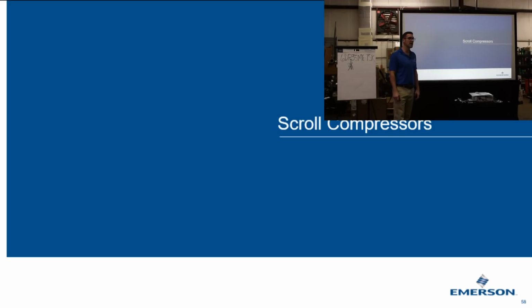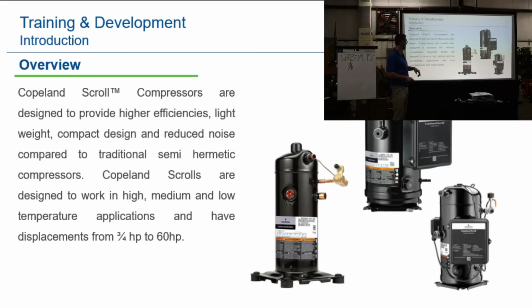Okay, scroll compressors. How many people work on scroll compressors today? Every hand goes up. Because this is most of my classes that I do, everybody works on scrolls. We're almost at the 200 million mark for scrolls. Back in 2017, we sold our 150 million scroll. That was 3 years ago. And we're making, I think, a minimum of 12 million scrolls a year. So we're closing in on 200 million scrolls. So there's a lot out there. Okay? And the big thing here, we have three-quarter horsepower to 60 horsepower scroll compressors. And you want to see a 60 horsepower scroll compressor, you're not moving that by yourself.